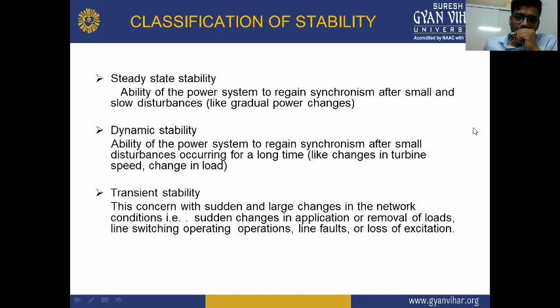Now, what is it? It is the maximum power that can be transferred without the system becoming unstable when the load is increased gradually under steady state conditions. For example, it is defined by P max, the maximum power that can be transferred without the system becoming unstable. The transient limit is the maximum power that can be transferred without the system becoming unstable when a sudden or large disturbance occurs.